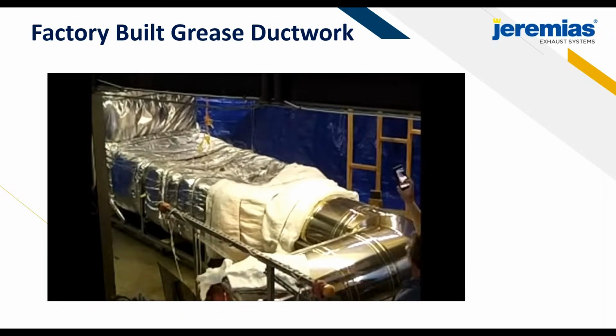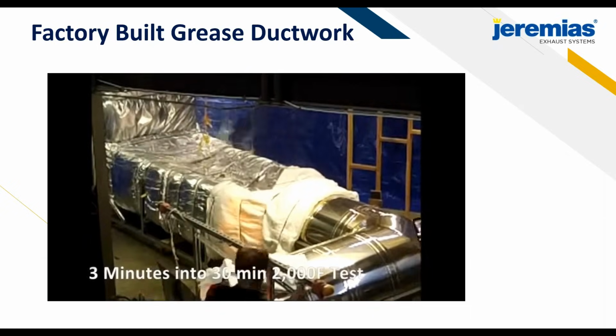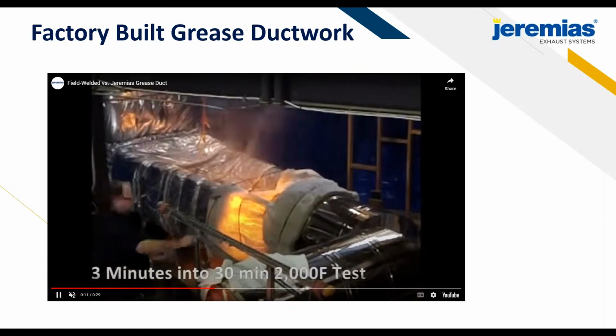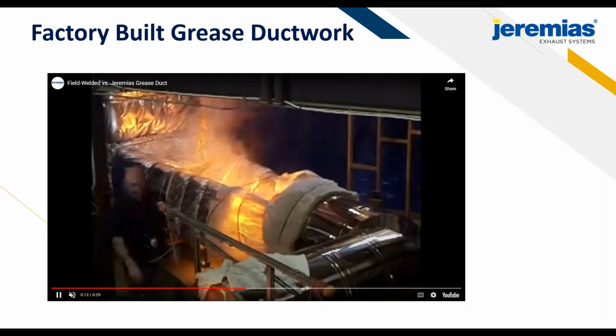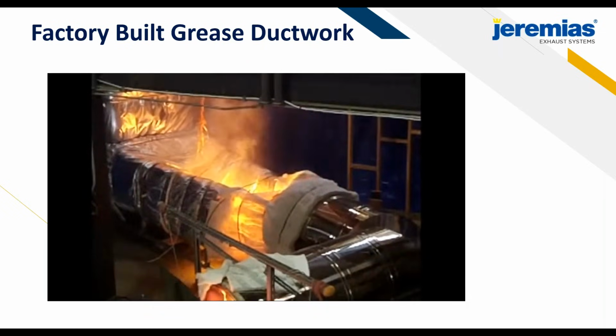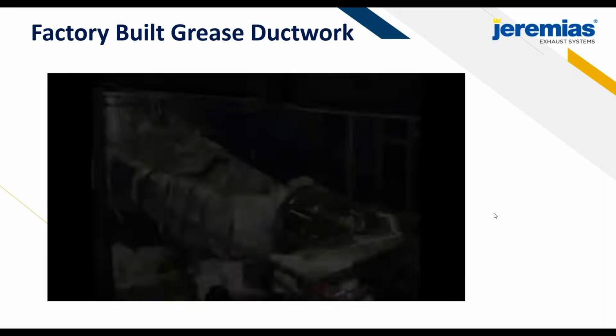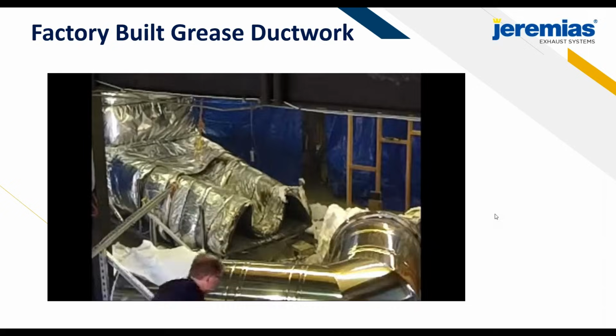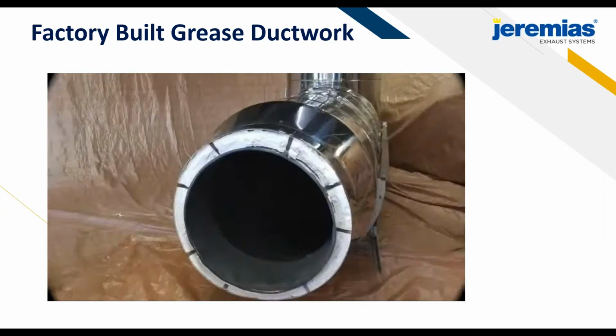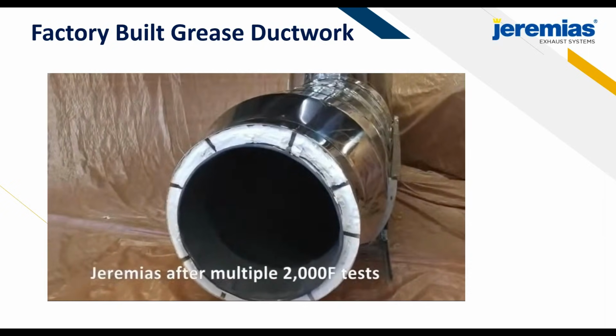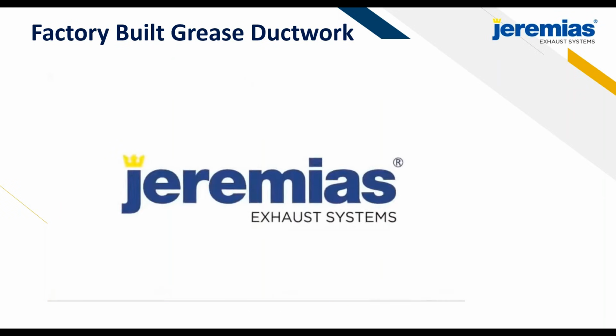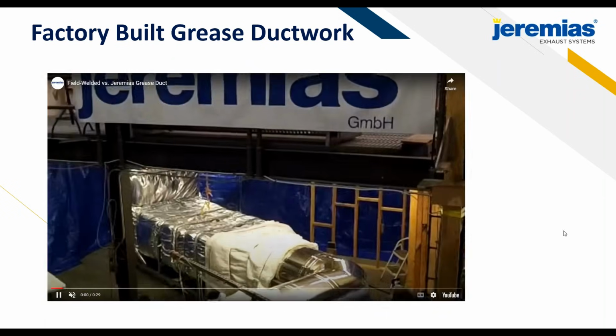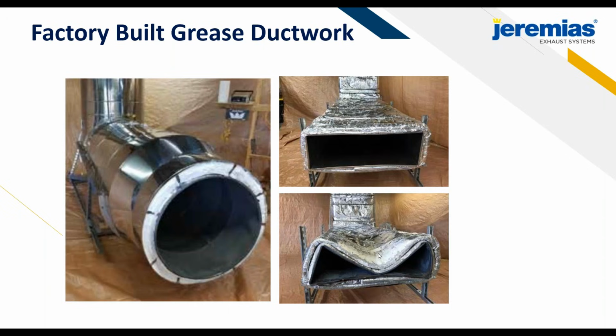So as you can see, that duct is 3 minutes into this 30-minute 2,000-degree test. That field welded duct is already collapsing, and the fire is basically outside the ductwork now. And as you pull it apart, you can see that it's pretty much completely collapsed, whereas the Jeremias duct is still intact and it contained all the fire as it needed to. So here's some pictures as well.